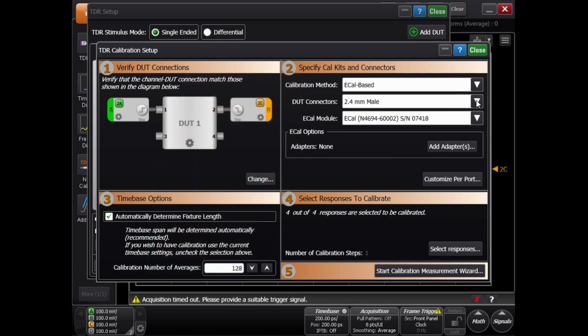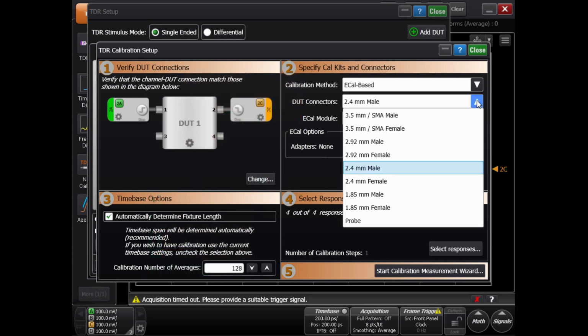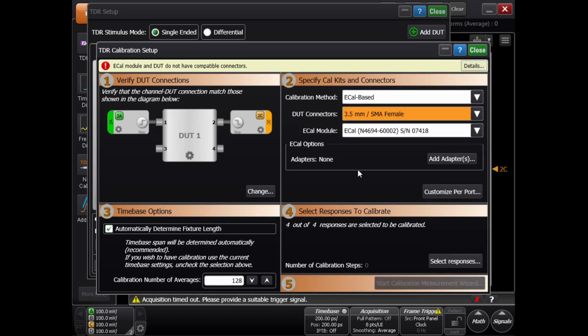The other situation I have is a board that's a 3.5 millimeter female connector. So if I'm going to test on that board and specify cal kits, I'm going to have to change a few things. First of all, I'm going to have to select the DUT. So the DUT here is a 3.5 millimeter female. As soon as I select that, we get an error up here. The Ecal module and the DUT do not have compatible connectors. They have to match. That's exactly what it's saying.